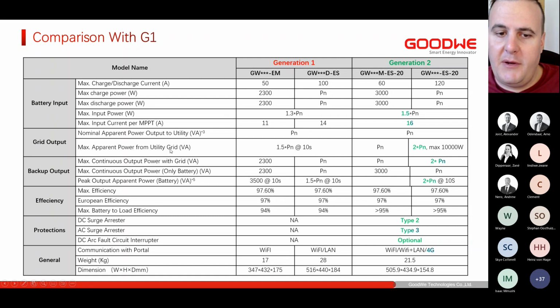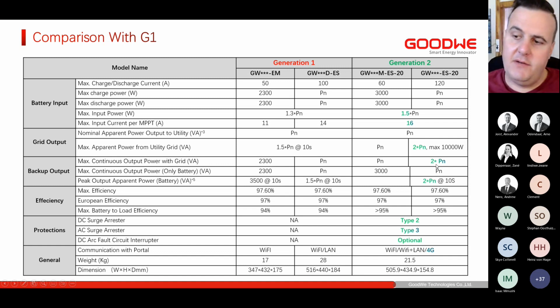The new max power from utility. We always have to look at that. Maximum can be 10 kilowatts. The 5 and the 6 do 10, and the smaller will do 2 times. So the 3 kilowatt does 6, and then the 5 and the 6 do a maximum of 10 kilowatts. Same for backup. You can have a continuous overload capability of 2 times, up to that 10 kilowatt as well. And that is constant as long as you have enough energy available.